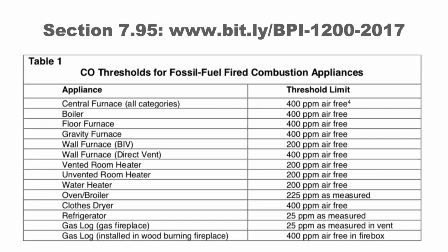Generally speaking, 400 ppm when measured on an air-free basis. However, ovens and broilers are as measured. That means the raw CO. Refrigerators, there are actually combustion refrigerators. Some of you might be familiar with that. They get as measured. Gas logs are as measured in the vent, and for gas logs installed in the fireplace, 400 ppm air-free in the firebox. So these have been developed by consensus with the manufacturers and other practitioners and those interested in the field.